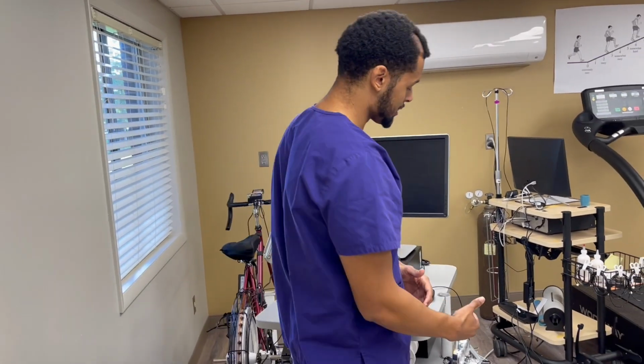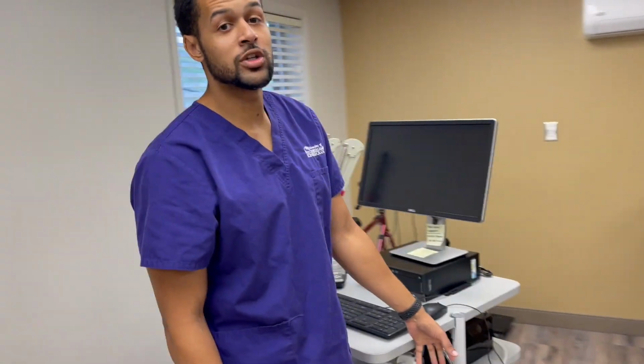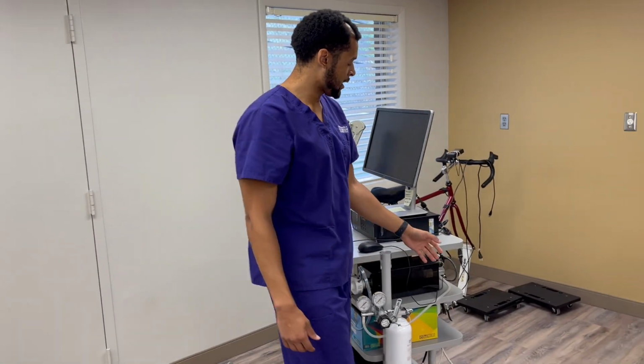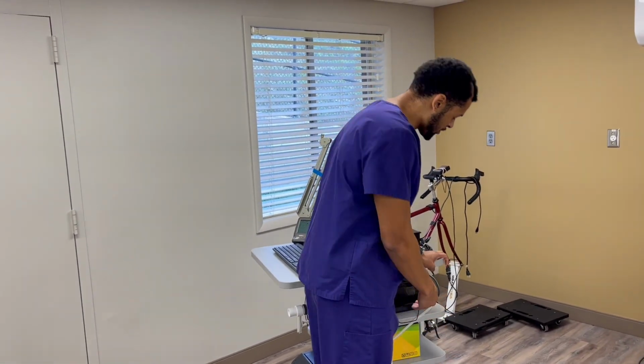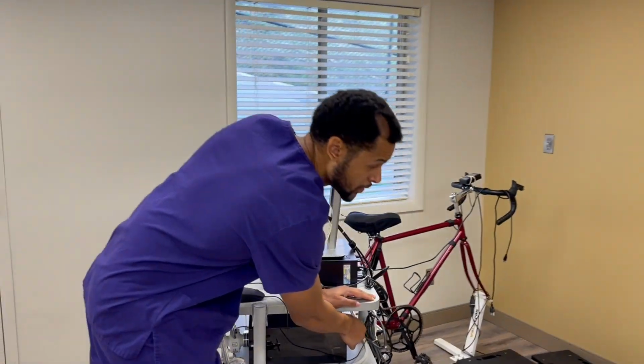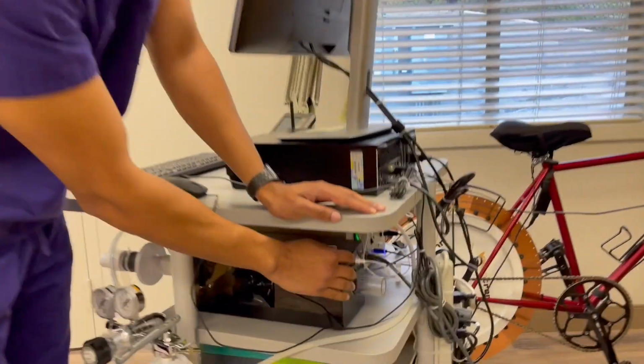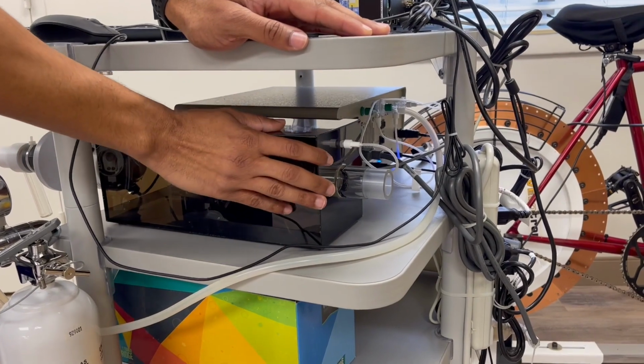Next, you walk around to the side and we have our gas calibration tank. And on the back, on the mixing chamber, there's actually a line, it's called the sampling line. And this is what you'll need when you're doing gas calibration. You'll need to remove that.